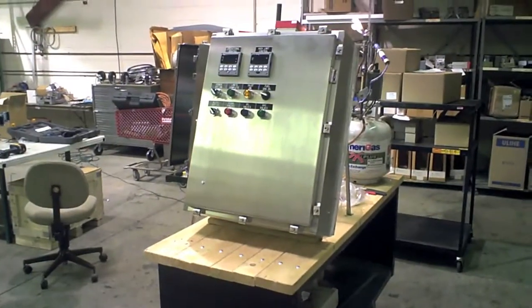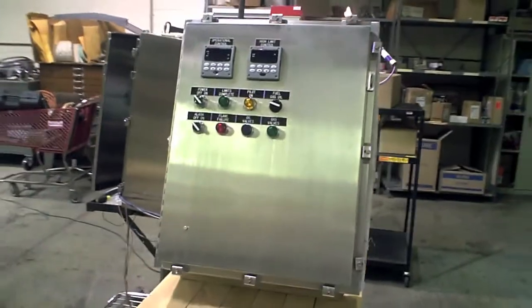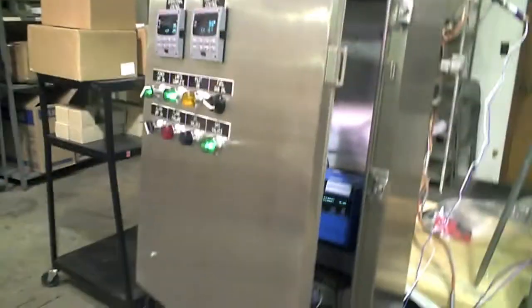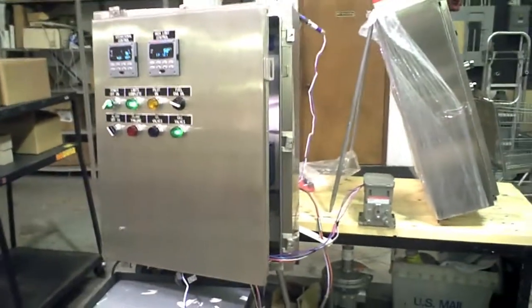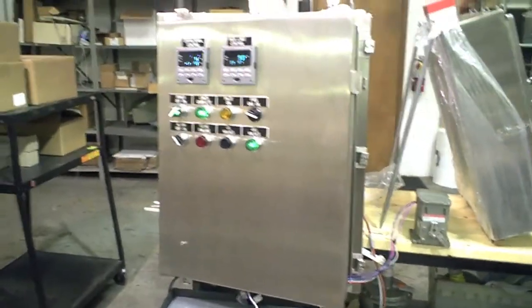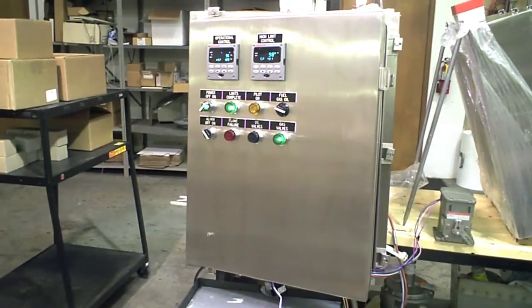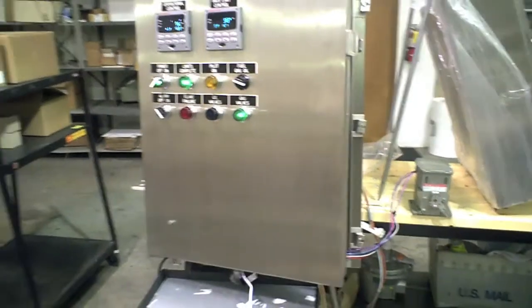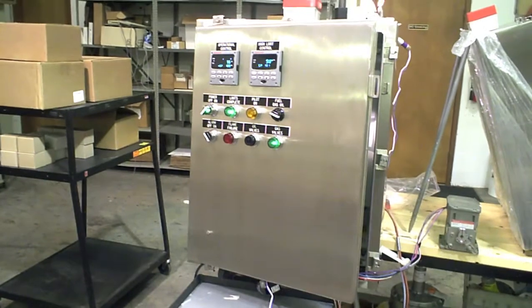What we have here are two stainless steel control panels — NEMA 4X — for a water pollution control center down in Clayton County. It is a pelletizing facility and we are upgrading the two 15 million BTU burners with Honeywell 7800 flame relays and Honeywell UDC temperature controllers.